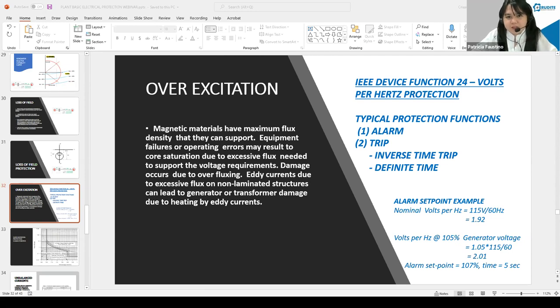Regarding how it happens, that's because of some operating problem, let's say the exciter is not working well. It's got trouble, either the exciter itself or the excitation control. There's a problem on the AVR and suddenly the voltage goes very high. That can be a cause of the problem. Excitation becomes the source of the problem, the exciter itself, or the AVR.